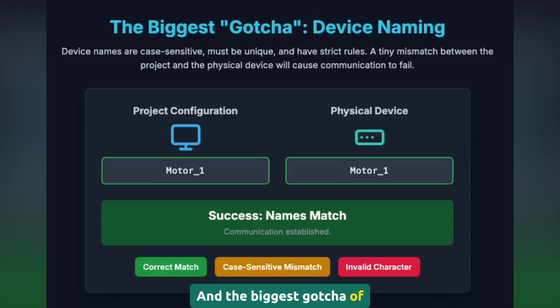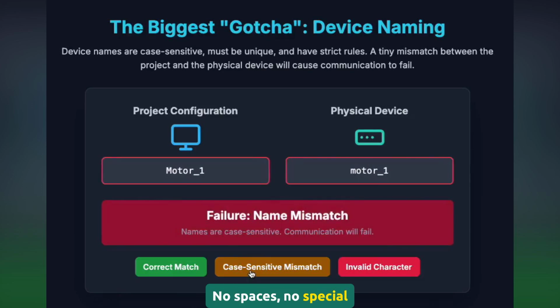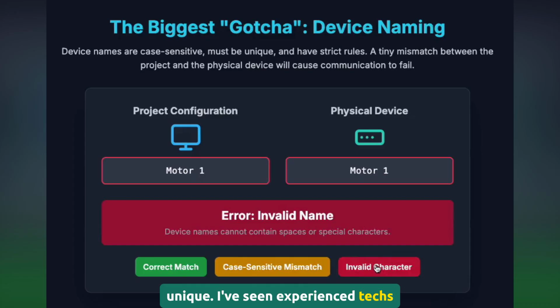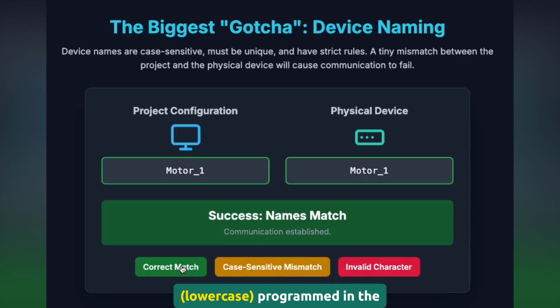And the biggest gotcha of all, device names are case sensitive and must follow strict rules. No spaces, no special characters except hyphens and underscores, and they must be unique. I've seen experienced techs spend hours troubleshooting only to find they had motor 1, capital M in the software, but motor 1, lowercase, programmed in the device.